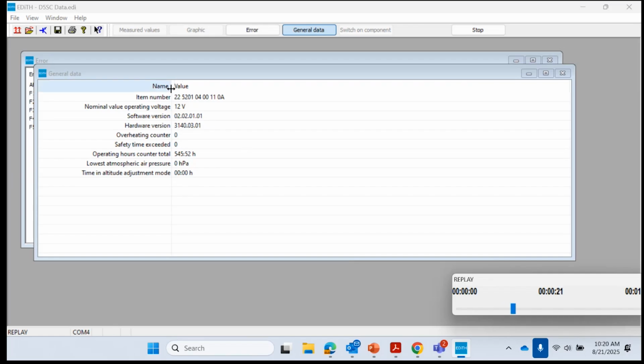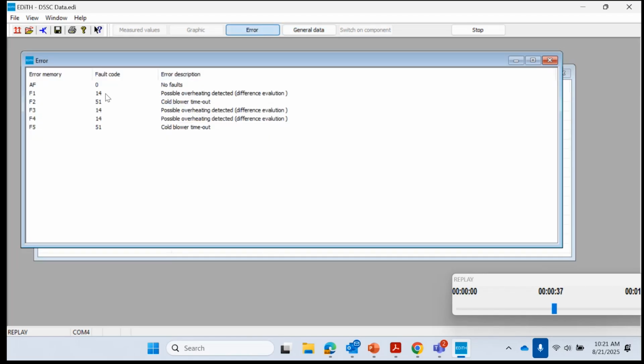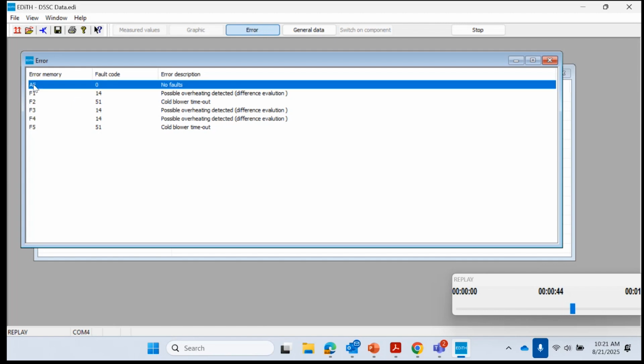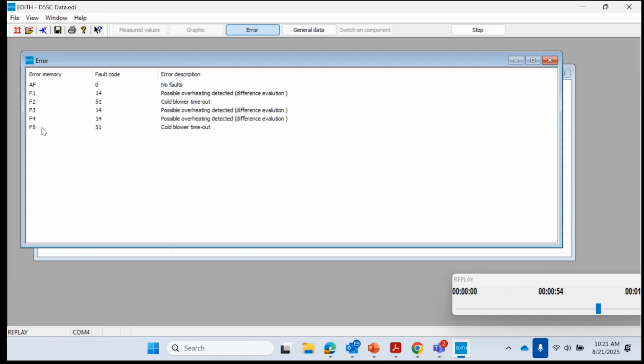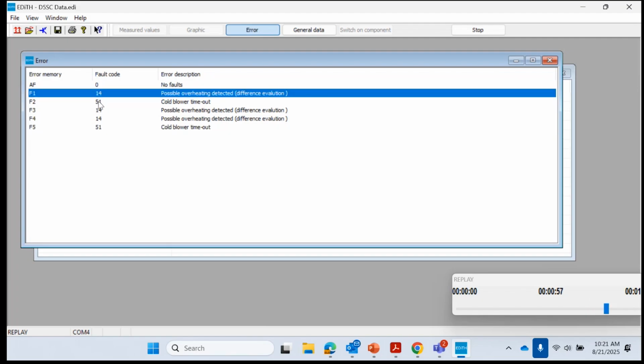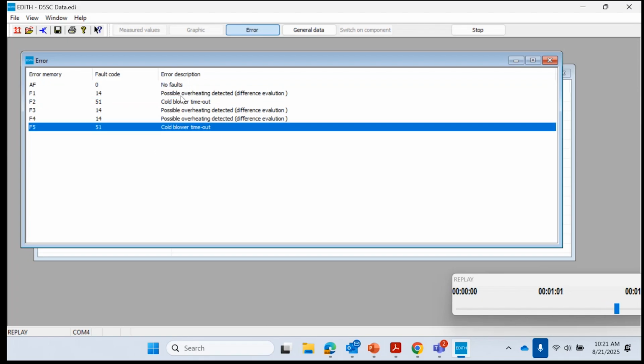You can see that it is showing us total hours of operation in hours and minutes. It is basically giving us a read of the overheating counter and the safety time counter. And in the back panel, which you can access by simply clicking on the error button here, you will see all the codes listed. Because this is a first generation heater, we have only one active code slot, and that slot right now reads a 0, which means no codes. And in the 5 storage memory slots, you can see we have codes beginning with a 14 and ending with a 51. We also have a small description, so you're able to read out both the code itself and the description.